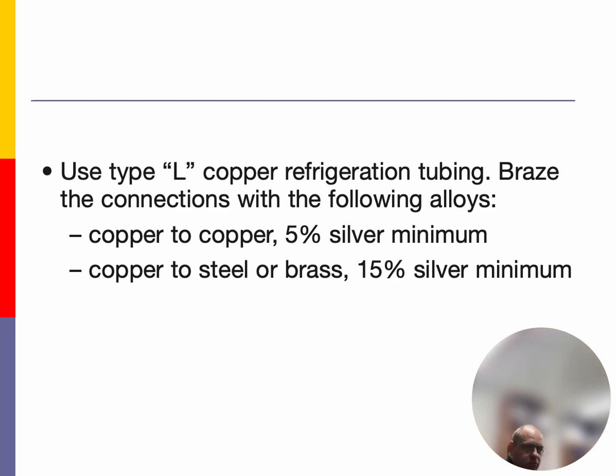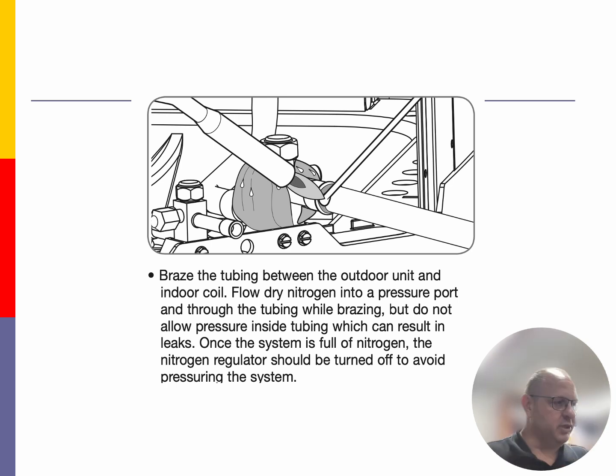So some more things that we want to try to accomplish with this: you want to wrap the valve very, very well. Otherwise, you're going to burn up the gaskets on the service valve. It's going to leak out the top of the cap when you go to take those caps off. You also want to be flowing dry nitrogen through those lines. Now, what this is going to do, it's going to go through the indoor unit and come back out. And as we are flowing that dry nitrogen through there, we are preventing the formation of oxidation. We are displacing all the oxygen out of the inside of the pipe, and then we are causing nitrogen to be in there and filled up so that we do not form scale on the inside of these pipes. Once again, scale's a problem, forms acid, blocks up metering devices. It's not a good thing. So flowing nitrogen is very, very important for us.